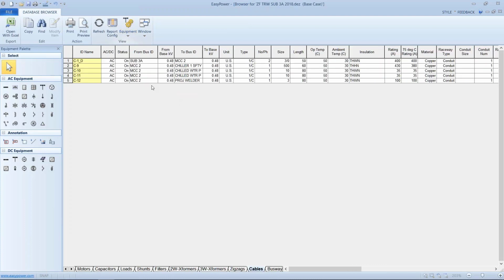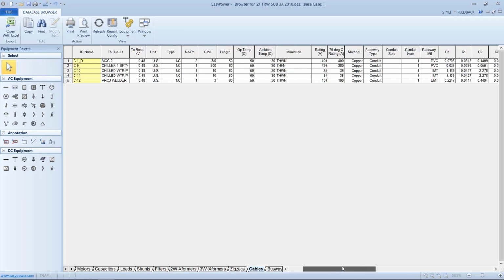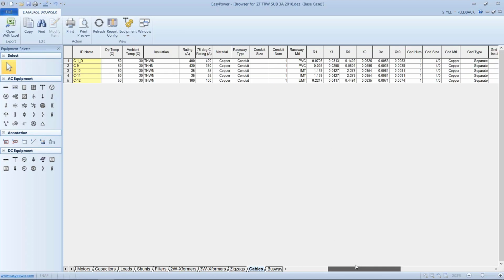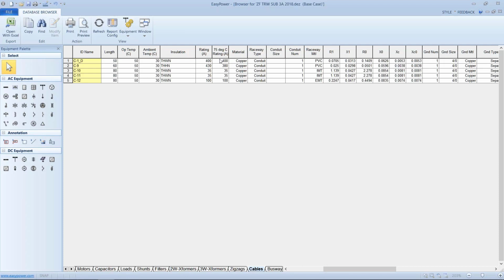And while I'm here, let's look at cables. This tool, Database Browser, is primarily useful for looking at the system from a 5,000 foot point of view. And what I'm looking for as I scan these different types of components is anything that could be missing, or incorrect, as far as the data collection. And one thing I want to look at as far as the cables is if my calculations for the reactive and resistive components have been completed, and if I have any elements that have temperature compensation that I would expect to see in these columns. And here I can see I have some kind of temperature compensation going on, but not necessarily in all of them. And again, this is more of a flag.